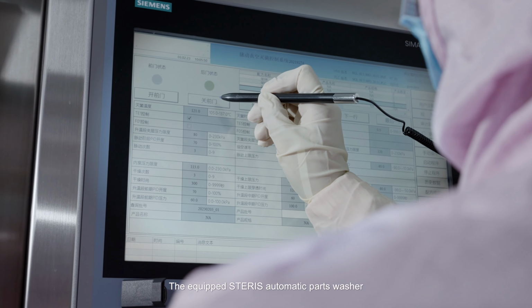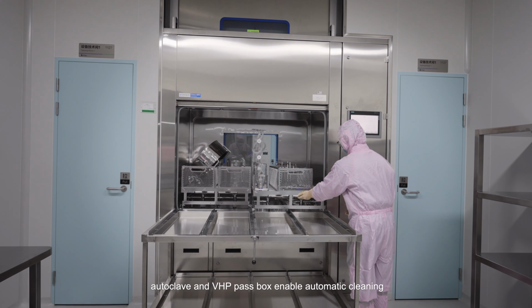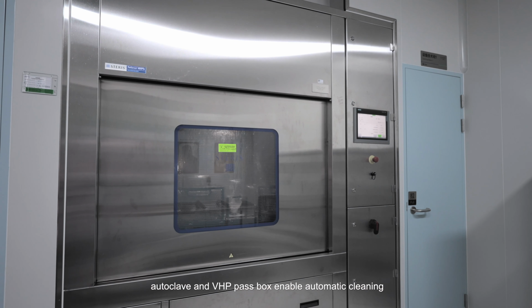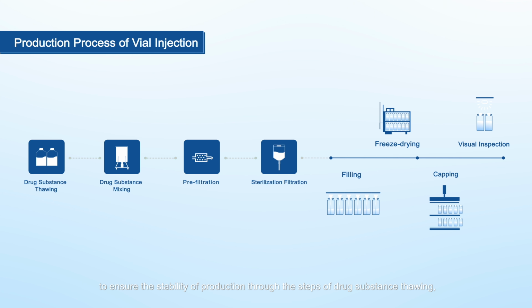The equipped Steris automatic parts washer, autoclave, and VHP pass box enable automatic cleaning, sterilization, and transference. A single-use formulation system is used to avoid cross-contamination with a temperature auto-control system. The production process in the workshop is under strict control by multiple procedures to ensure the stability of production through the steps of drug substance thawing, drug substance mixing, pre-filtration, sterilization filtration, filling, freeze-drying, capping, visual inspection, and secondary packaging.